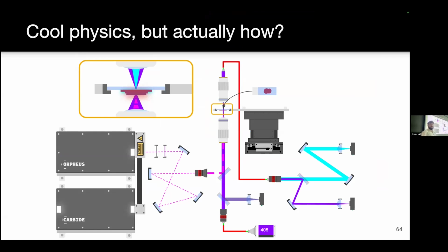So that goes into laser physics. This is the actual laser, and then this is what's called an amplifier. This excites at a wavelength of 1016 nanometers, which is far in the IR range, and then this will take that 1016 and do some cool physics to output whatever wavelength you want. The reason this is necessary is because, remember on the absorption spectra, different molecules absorb differently. So we want to use this to move along the spectra so we can pinpoint specific molecules we're interested in.